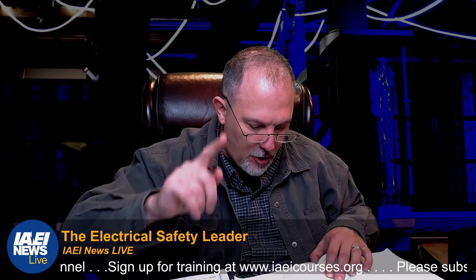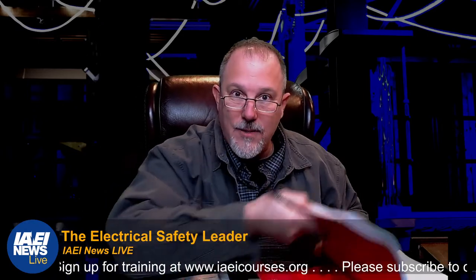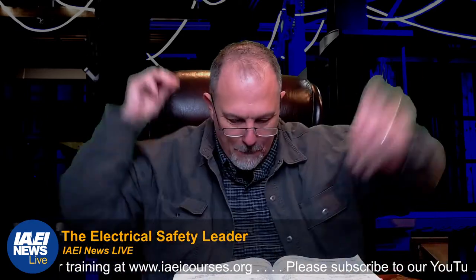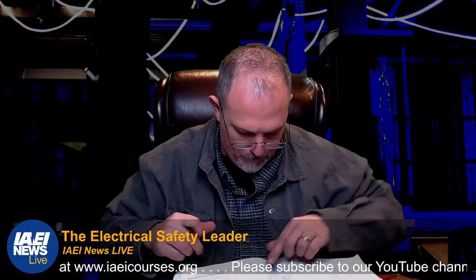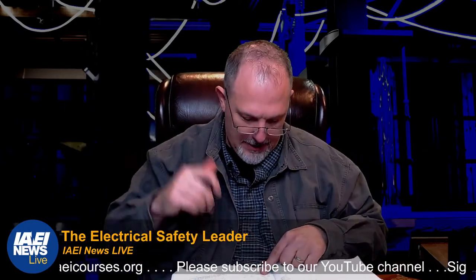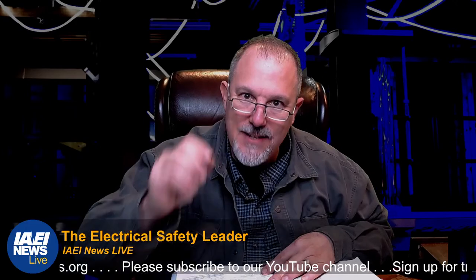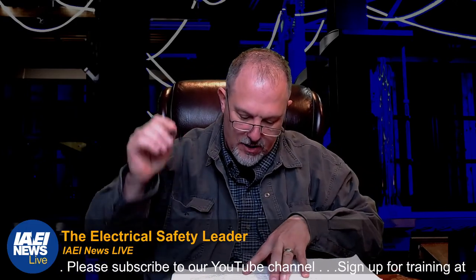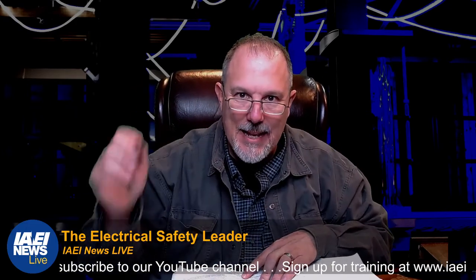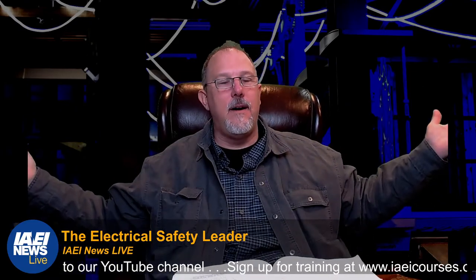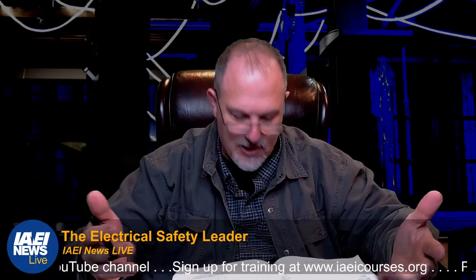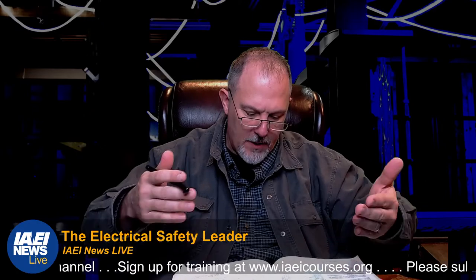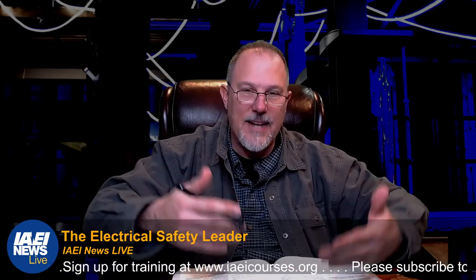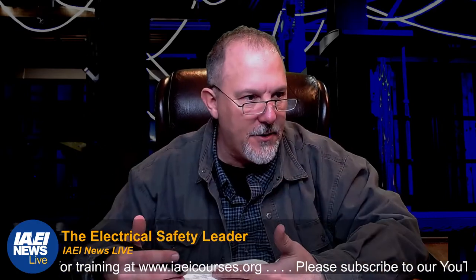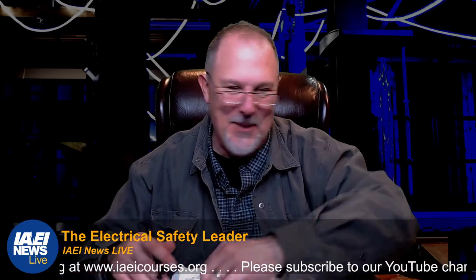But are you required to install only listed products? Yes, you are. 706.5 says energy storage systems shall be listed. That makes life a lot simpler. 706.4 just tells you what has to be marked on it per the standard.